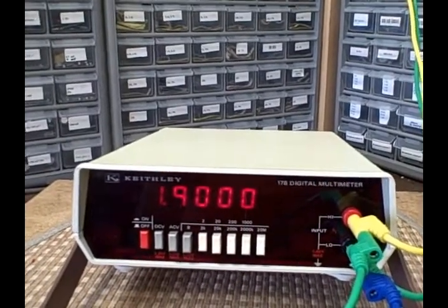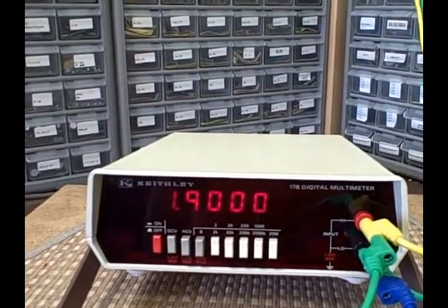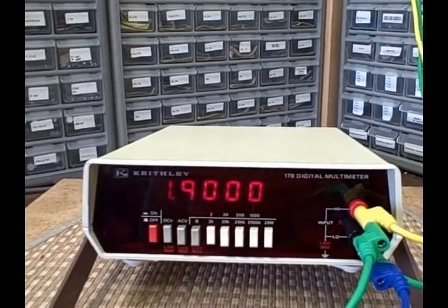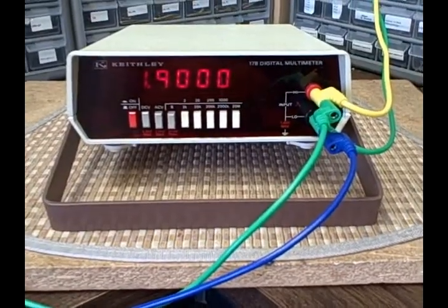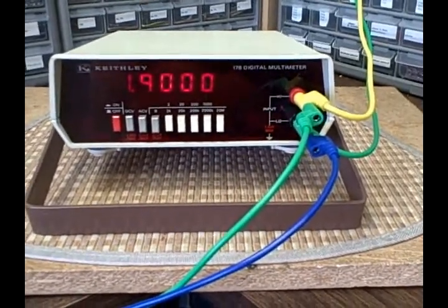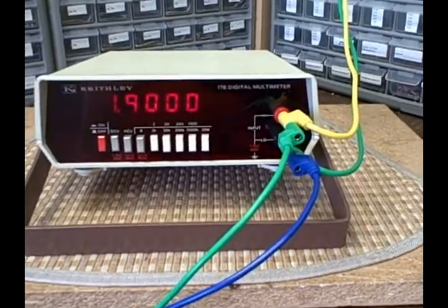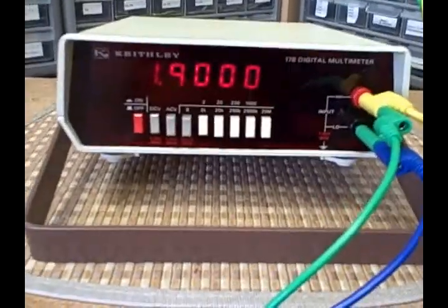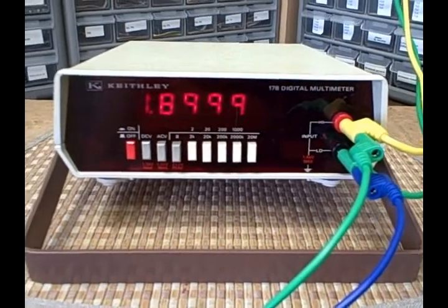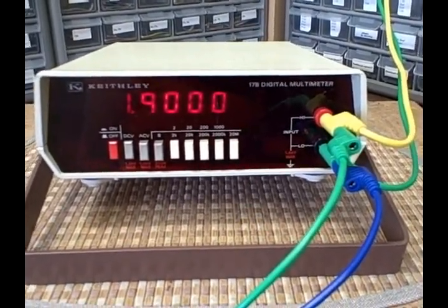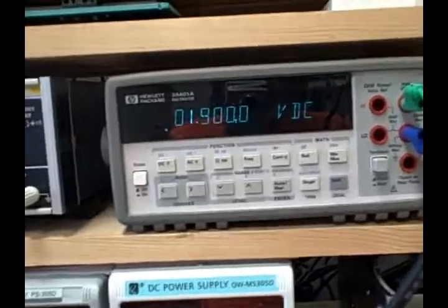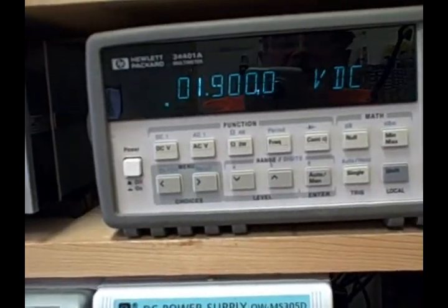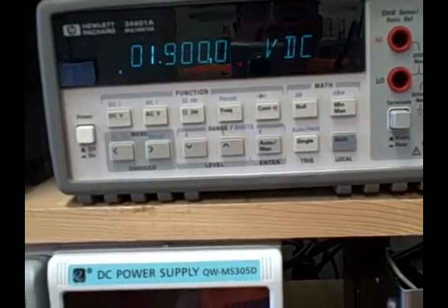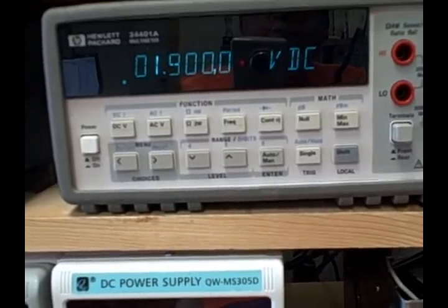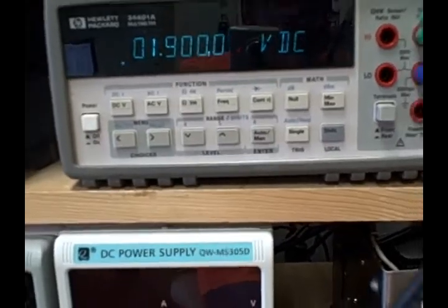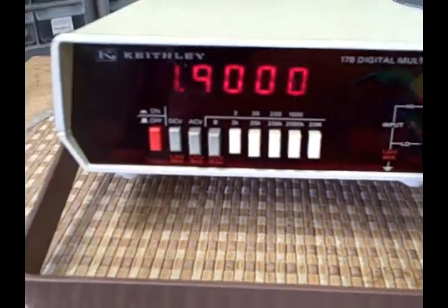We'll read anything from DC 2 volts full scale to 1000 volts full scale. The Keithley 178 is a 4.5 digit digital multimeter. So what that means is you can get 5 digits, as you are seeing right now on this display. So we're reading 1.9000 volts. And my recently calibrated Hewlett-Packard 34401A, which is a 6.5-digit unit, is also reading 1.9000 volts. So they're both in wonderful agreement.